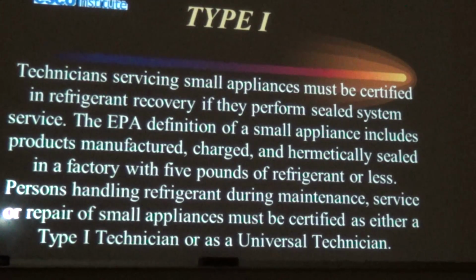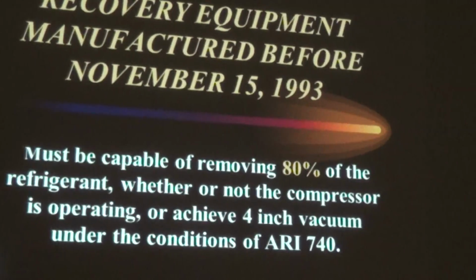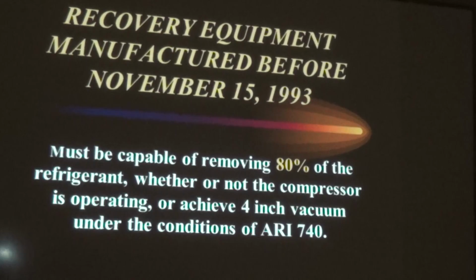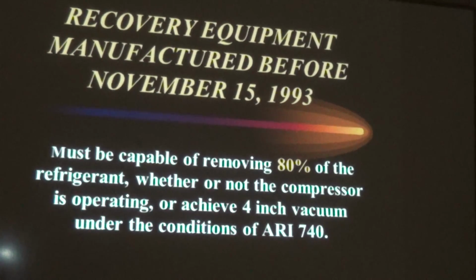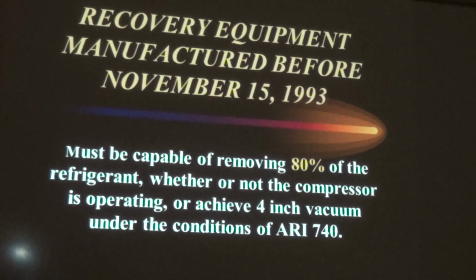So a Type 1 appliance is any appliance, like I said, that holds 5 pounds or less of refrigerant. Who can work on it is any tech who has Type 1 certification, or universal certification. Recovery equipment manufactured before November 15th, 93. Now we're going to get into this whole 80% and 90% rule that you have encountered before. So if the machine was made before 93, it must be capable of removing 80% of the refrigerant, whether or not the compressor operates, or achieve a 4-inch vacuum under the conditions of another standard, ARI 740.